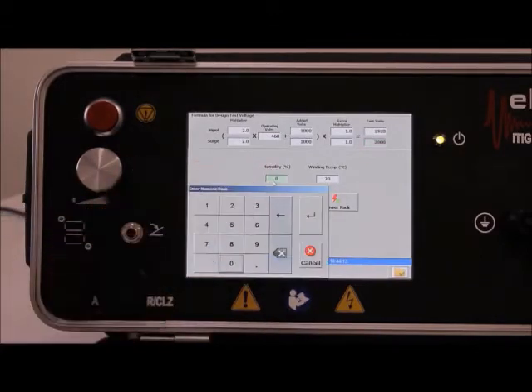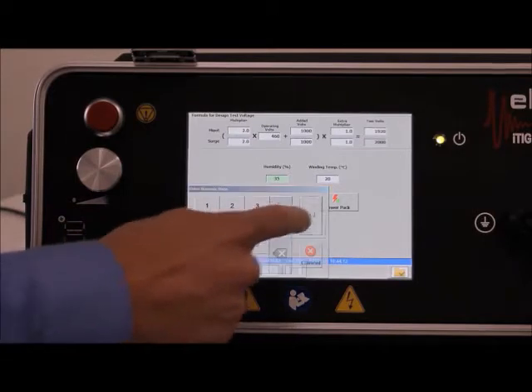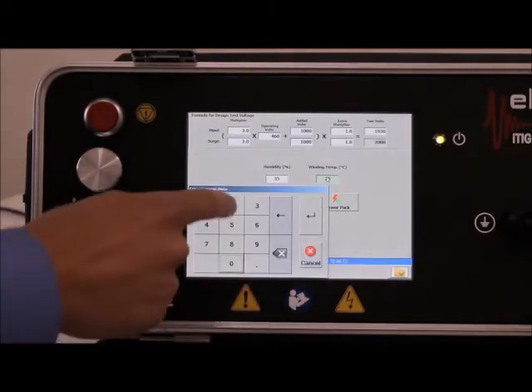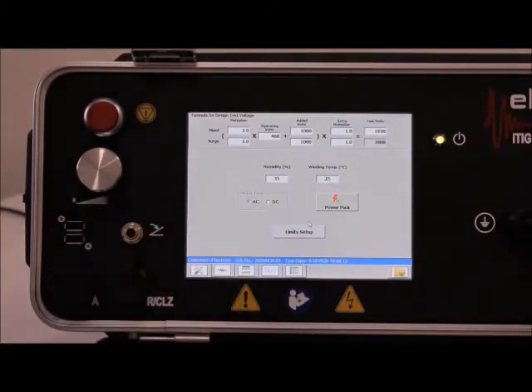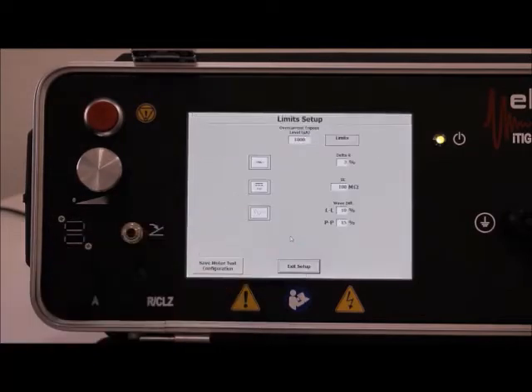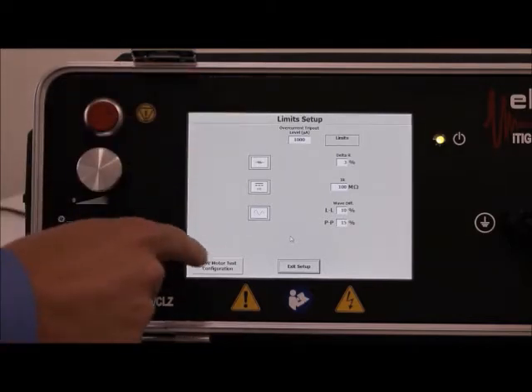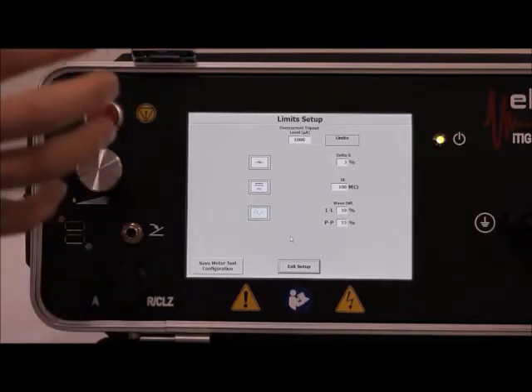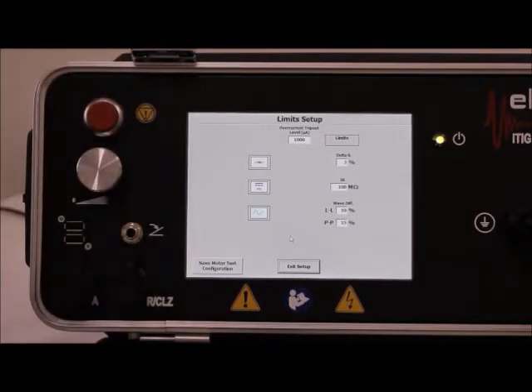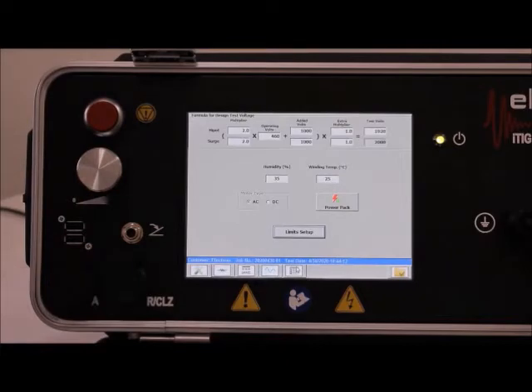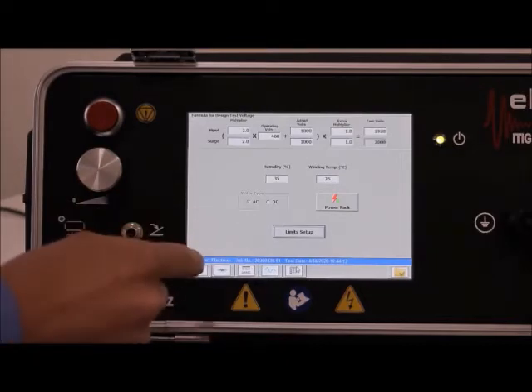Humidity, let's say it's a nice dry day in Colorado, 35%. Temperature, maybe it's a nice hot summer day, 25 degrees. Limit setup. Default settings in this case are okay. If you would like to change any of these, click the white field and change them. After that, you can say save motor test configuration. This will then be stored for this serial number. No need to change it again. Exit setup. We're now going to start our test sets here.